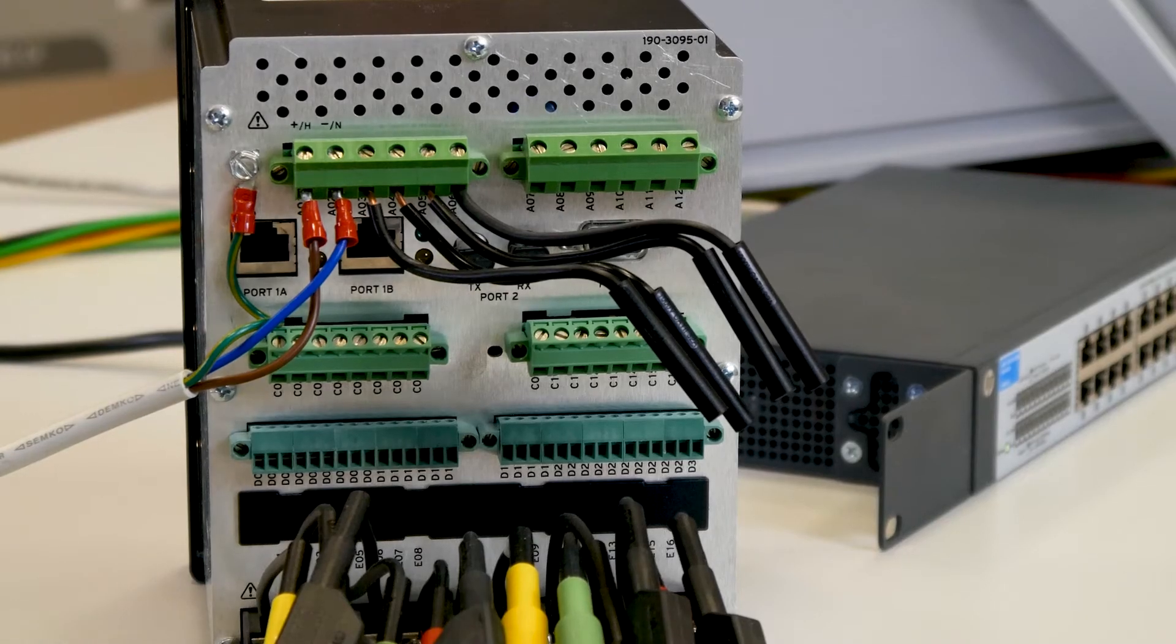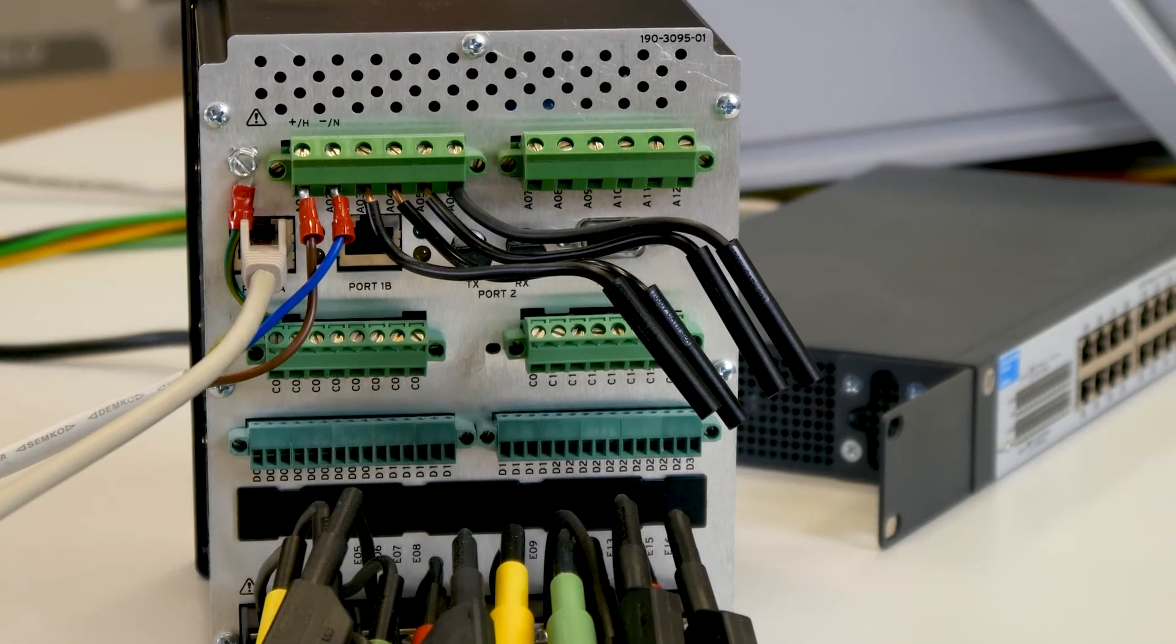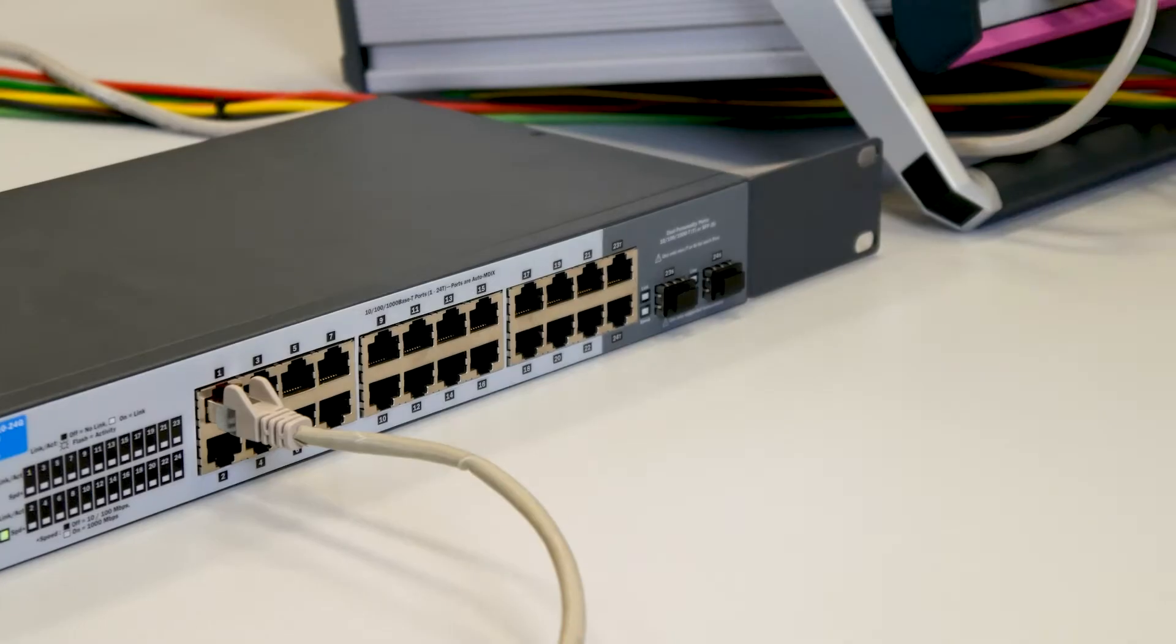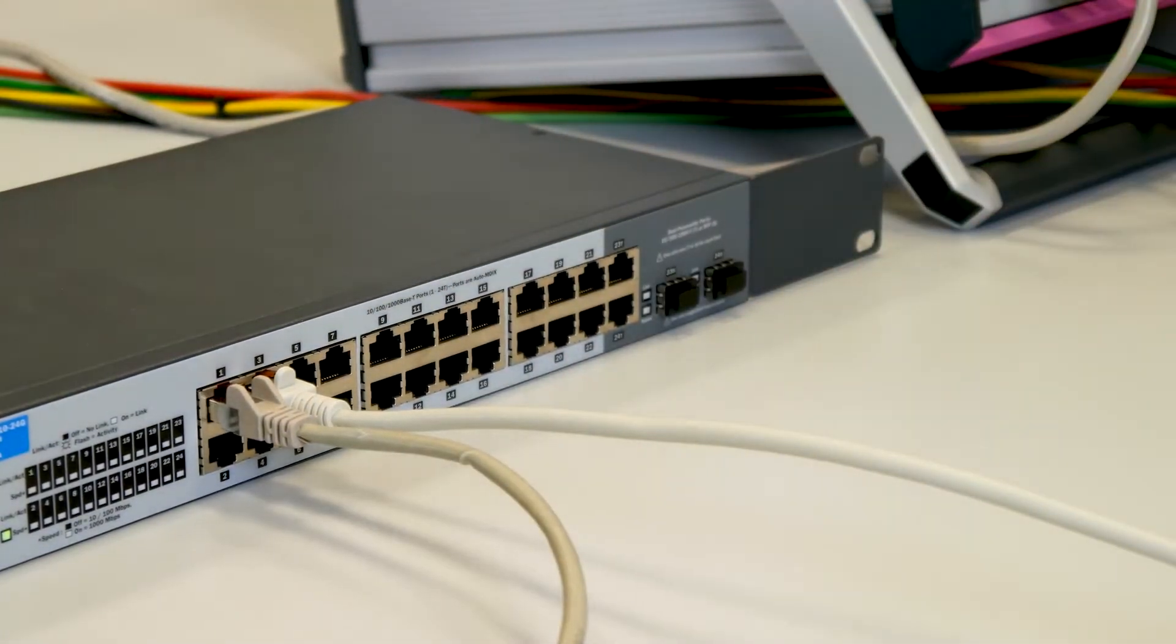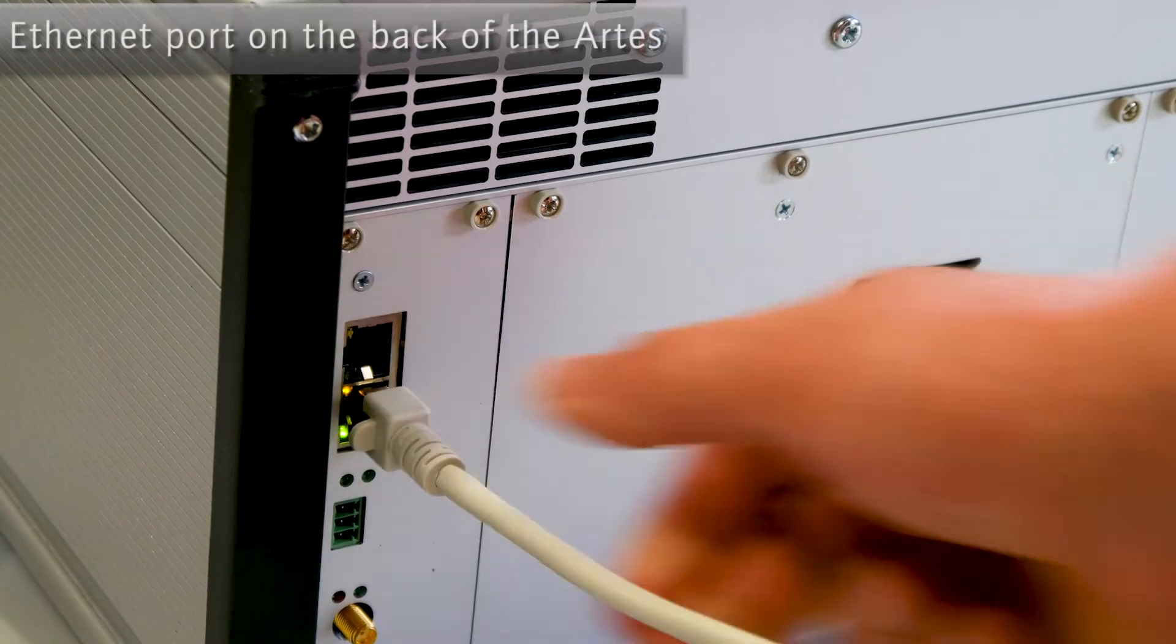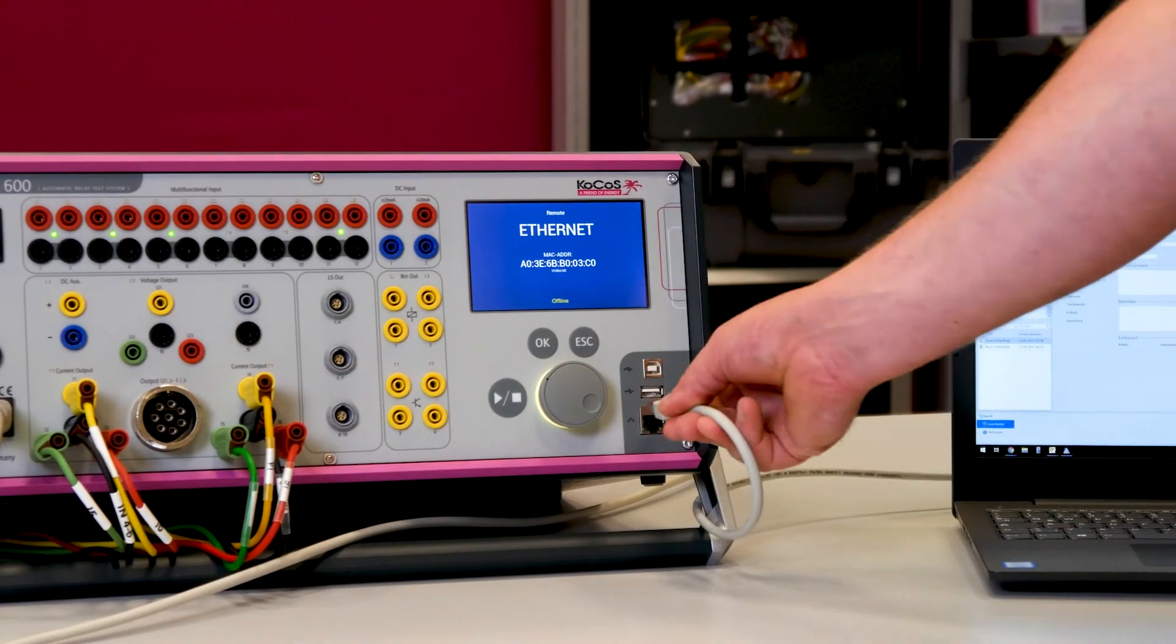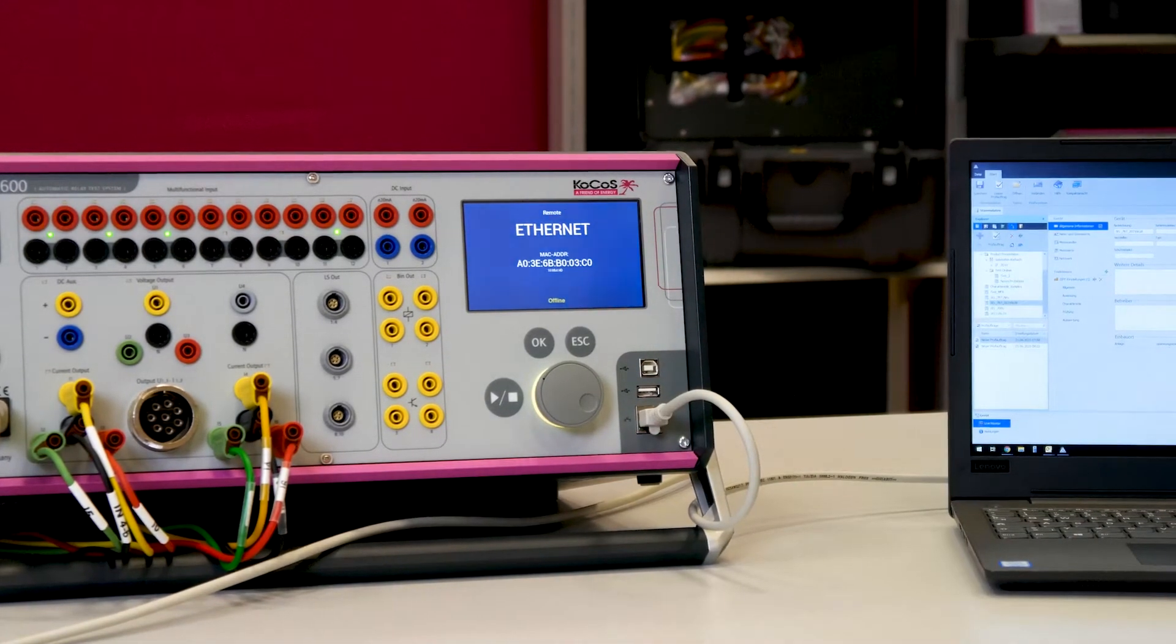In order to be able to record and evaluate the goose messages sent out by the test object during the protection test with the Artes, a connection must be established between the process bus and the test system. The Ethernet port on the back of the Artes is used for this purpose, as it is directly connected to internal signal processor, thus minimizing runtimes.